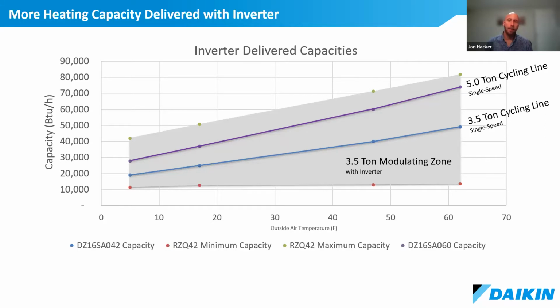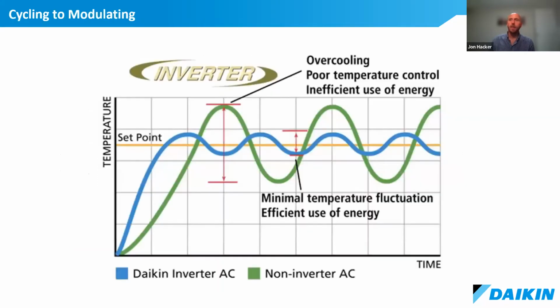As just a point of comparison, I've also added a 5-ton system that's cycling, and comparing it to the capacity at 5 degrees Fahrenheit for the 3.5 ton, it can even provide more heat than that. So I think maybe this might address Susan's question, or if this slide doesn't, maybe the next few will. This is a simplified take, and I'll show a more complex take on the next 2 slides on what happens with an inverter and some of the impacts to temperature, and then specifically on the next few slides, kind of operationally what's happening within the heat pump.